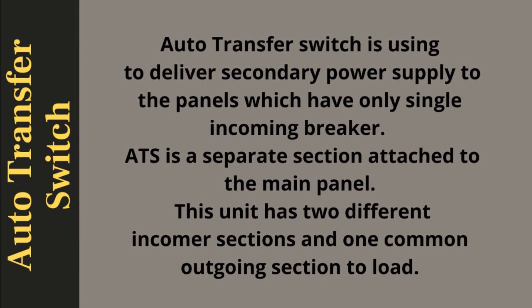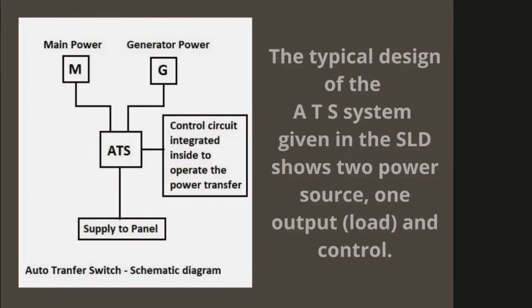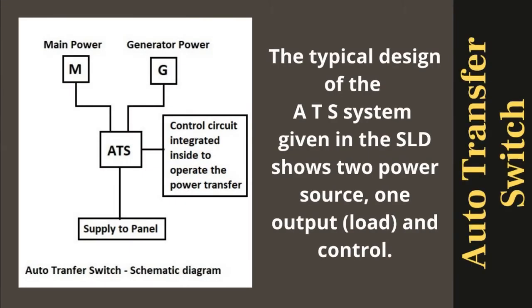Auto transfer switches are used to deliver secondary power supply to panels which have only a single incoming breaker. ATS is a separate section attached to the main panel, with two different incomer sections and one common outgoing section to the load. The typical ATS system design shown in the SLD includes two power sources, one output, and control.